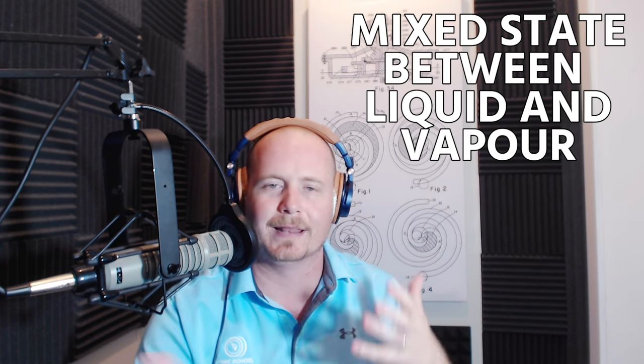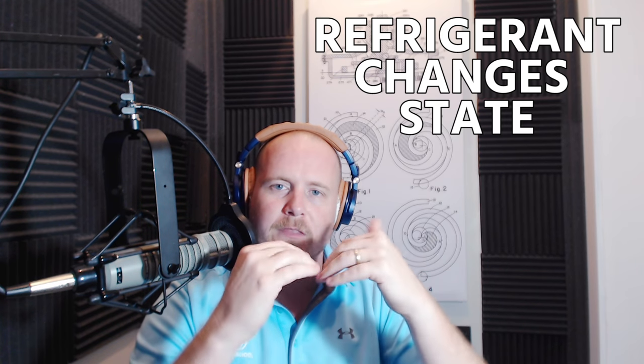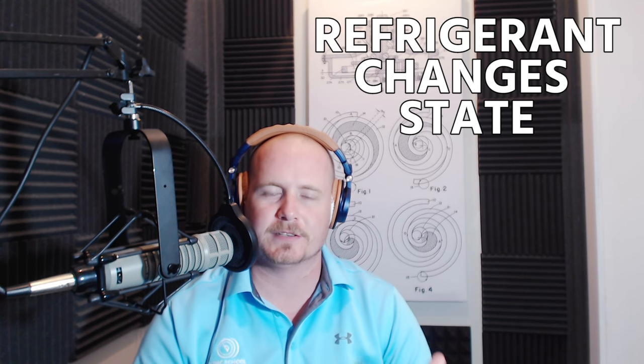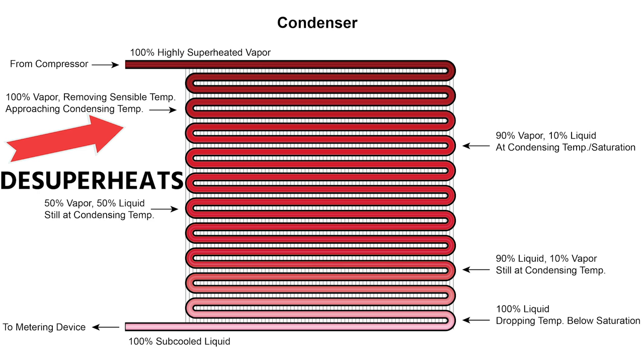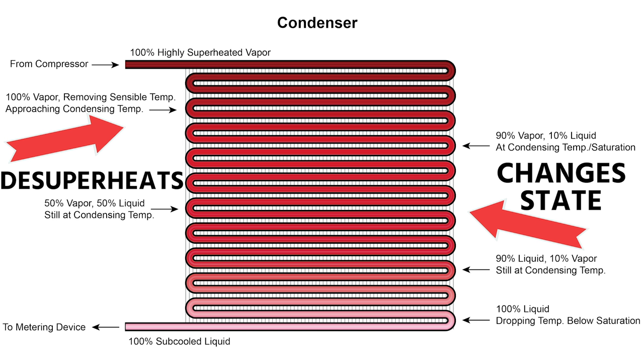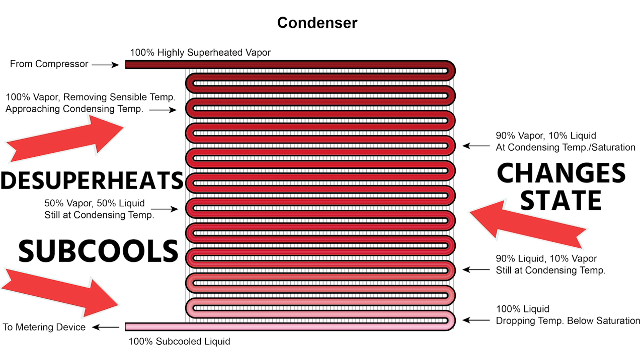Saturation is a word that many technicians misinterpret. You can look it up on the HVAC School website, which has articles and podcasts on saturation. It's the point at which the refrigerant starts to change state. In the condenser, we're changing from vapor to liquid: first it desuperheats, then it changes state — so the big center portion of the condenser is changing state from vapor to liquid — and then at the end it sub-cools, which means it drops temperature below the condensing temperature, or below saturation.